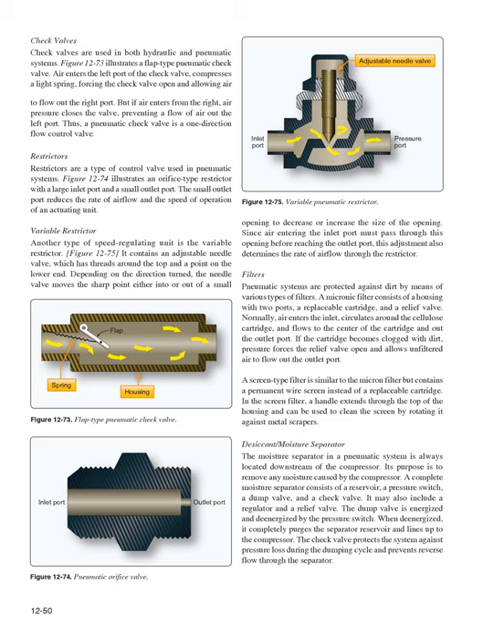Restrictors. Restrictors are a type of control valve used in pneumatic systems. Figure 12-74 illustrates an orifice-type restrictor with a large inlet port and a small outlet port. The small outlet port reduces the rate of airflow and the speed of operation of an actuating unit.